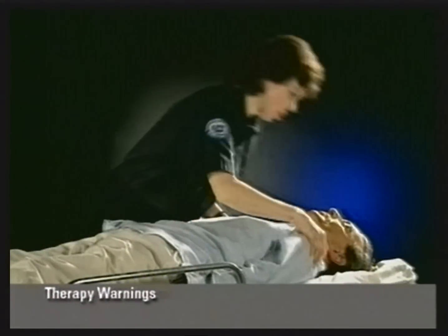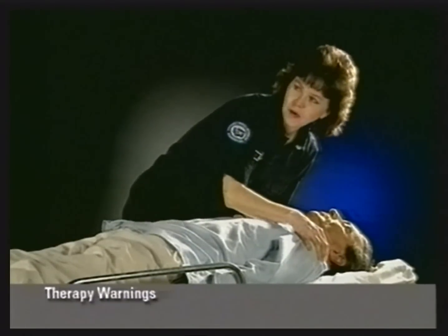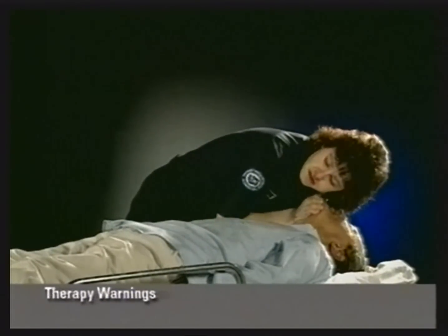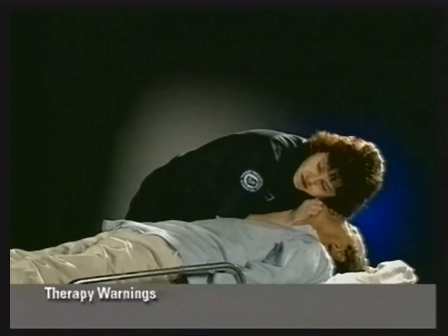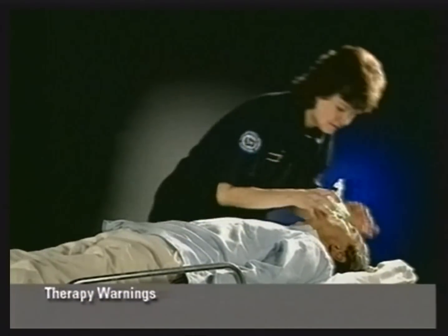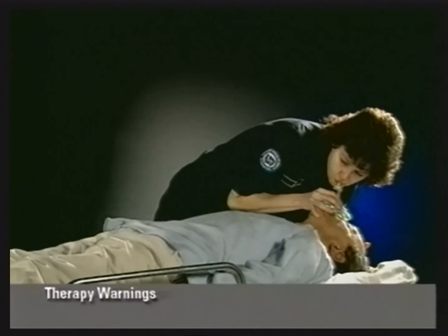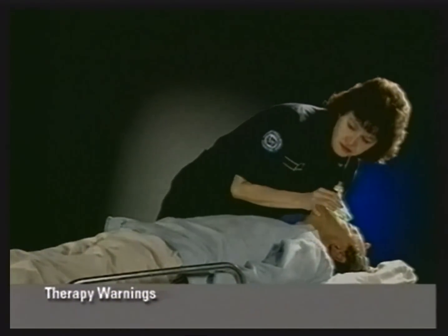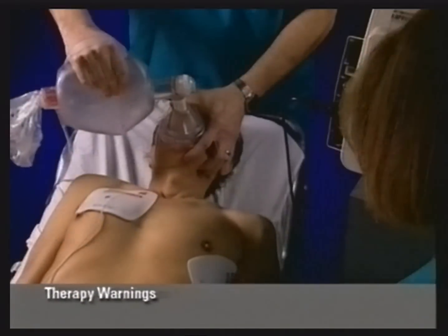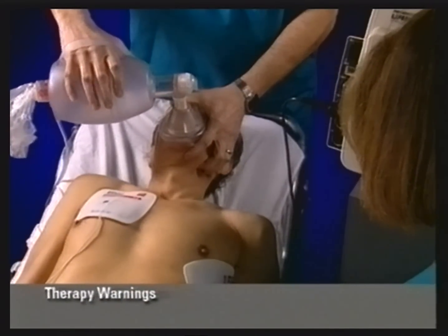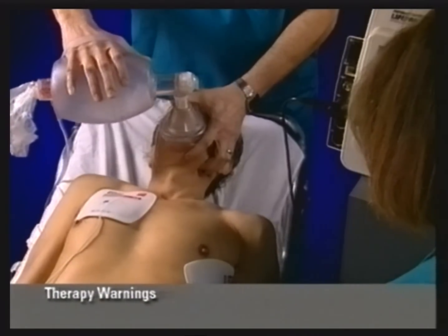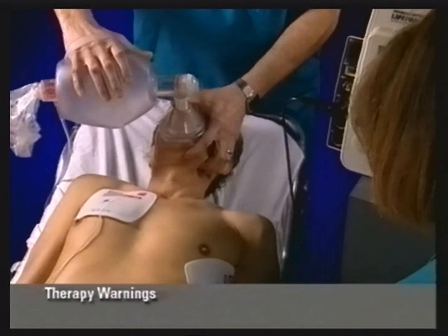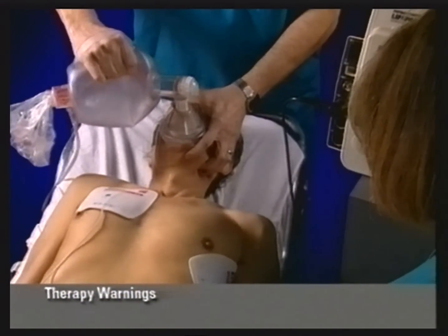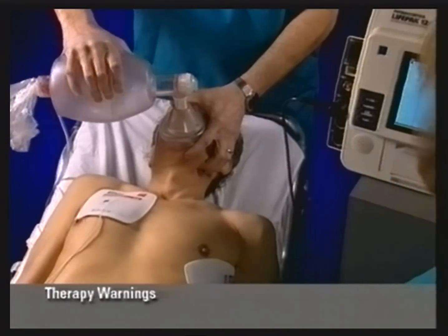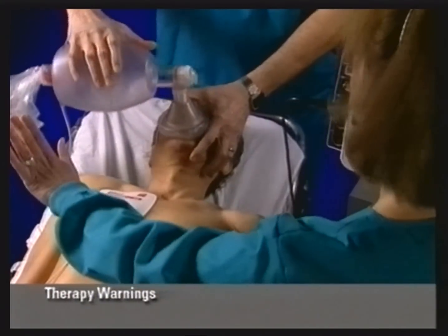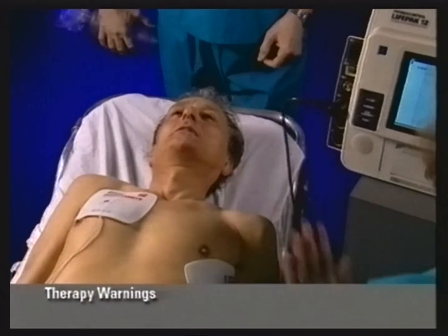Here are some key items to remember. AED, or advisory mode, is to be used only on unconscious persons, not breathing, and without a pulse. It is not designed to be used on infants or children younger than 8 years old because of the high energy levels. Do not use the defibrillator in the presence of anesthetics or other flammable agents. Use care in the presence of oxygen. An electrical arc may cause a fire or explosion. Turn off or remove the oxygen source prior to shocking the patient.